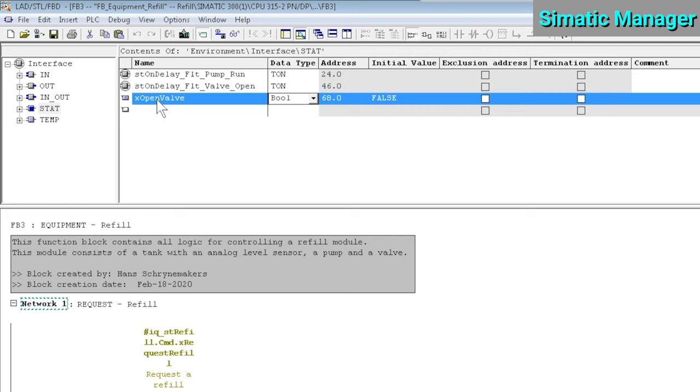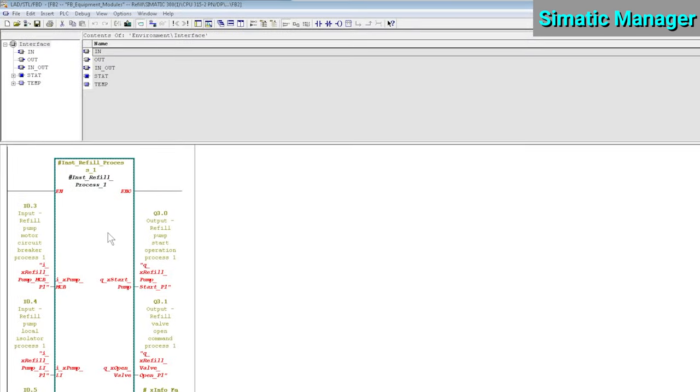I'll show you why that's not a good idea. Let's close this block and go back to where this function block is called. Now you can see that the call of the function block is displayed in red. The block call is invalid now because we changed the block interface by adding that boolean variable. What we need to do here first, before downloading the function block itself, is to manually update all block calls.